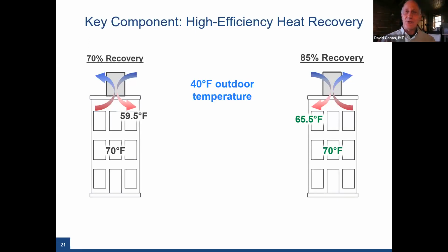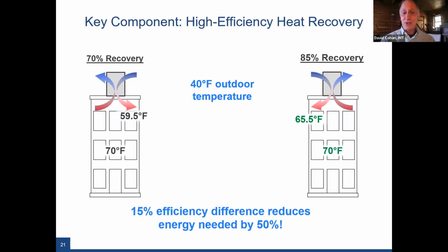On the left, if you recover 70% of the energy with your heat recovery unit, that delivers 59.5-degree air. On the right, if it's 15% more efficient—so 85%—that delivers 65.5-degree air. You might think, well, a 15% difference in efficiency, how big a deal is that? It's huge, because the gap from 59.5 to 70 degrees is 10.5 degrees, while the gap from 65.5 to 70 is only 4.5 degrees. So you only need half the energy to keep that building warm with the higher efficiency unit.